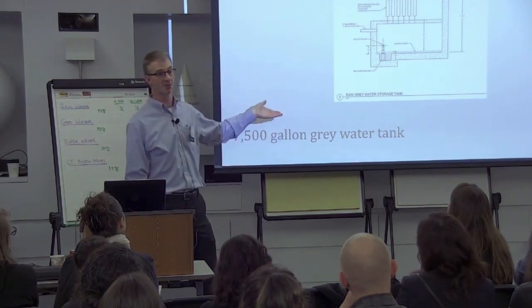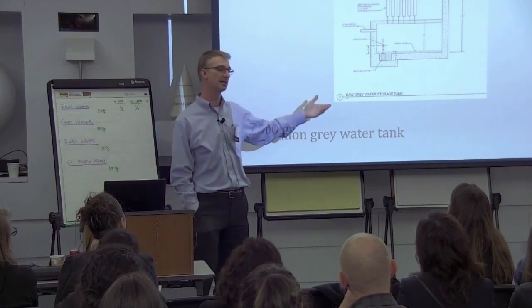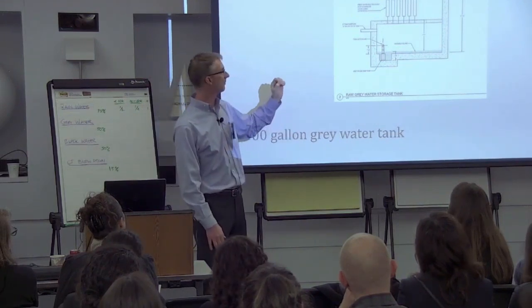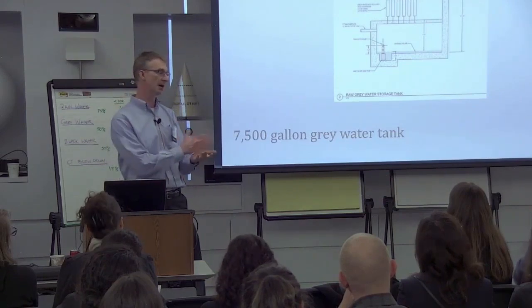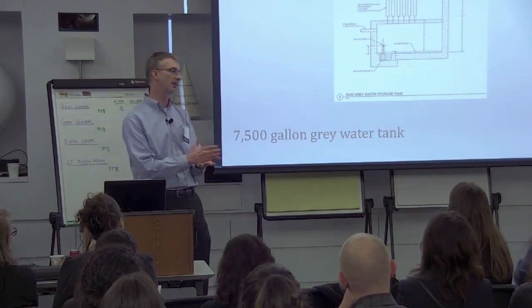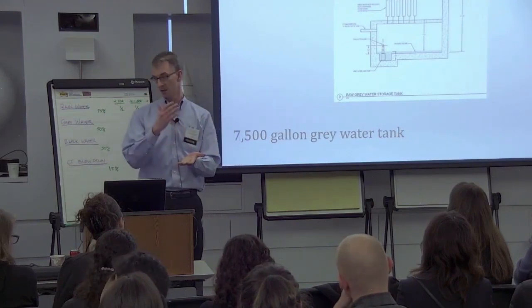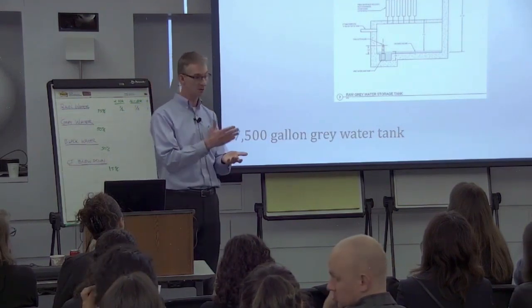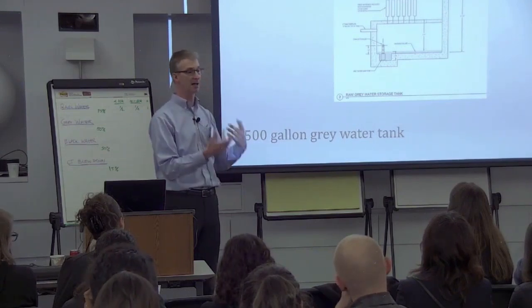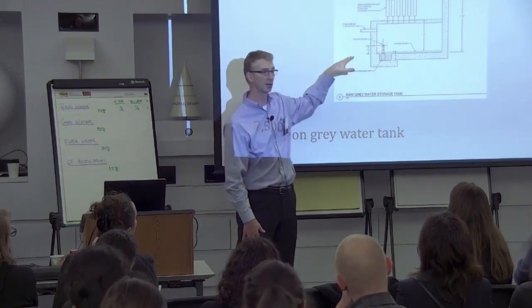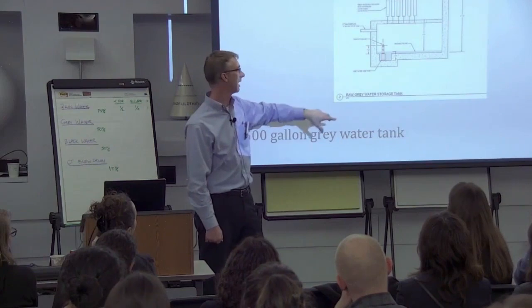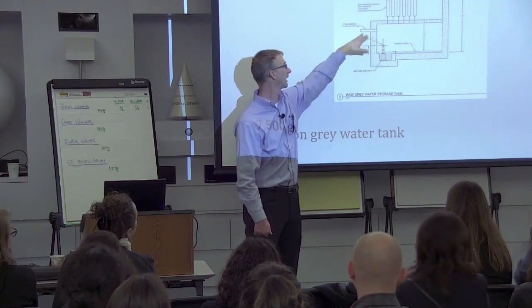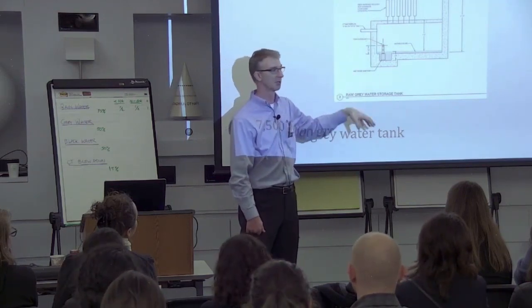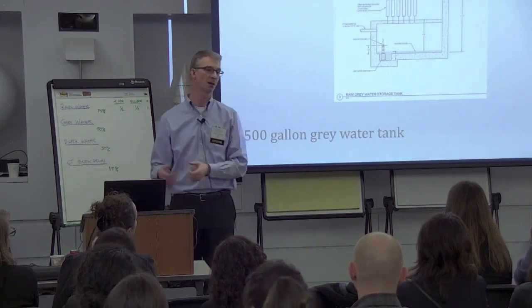Because we will be getting rainwater, we have to prioritize its use. The nice thing about the system, since we are meeting our flushing and irrigation load, and quite a lot of our cooling tower load with rainwater and gray water, we are allowed to divert any excess gray water we get on any given day to storm or sanitary sewer. So we can control how much gray water we take in by letting any excess just go to the sanitary sewer, because we're more than meeting all of our required demands.